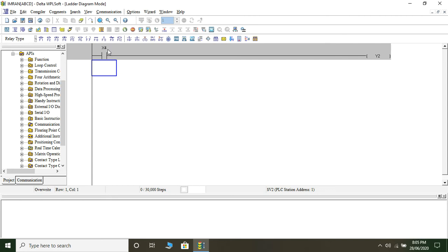You can have as many number of inputs as you want on one rung, however the output contact should always be one. In this case we have one input and one output. The input is always to the left side of the output. You can connect inputs in series or parallel on one rung, but every rung can have only one output, placed at the extreme right. The left rail is connected internally to a positive supply and the right rail is connected to ground, so current moves from left to right, passes through the load, and gets grounded.